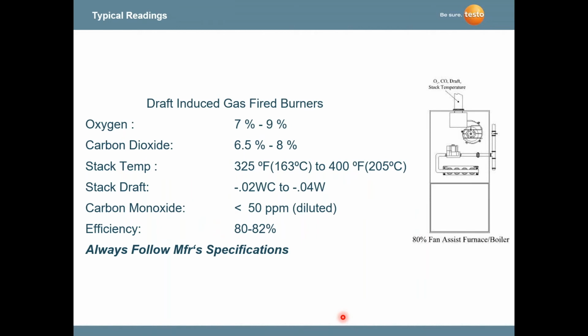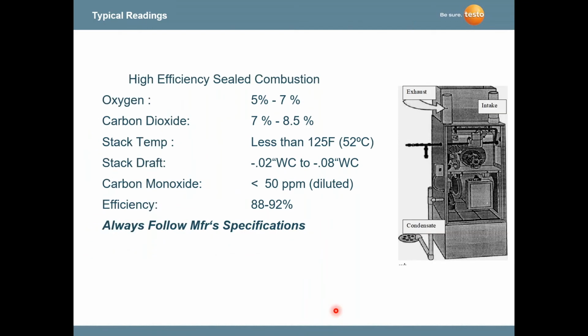Draft-induced gas-fired burners, again, here are some areas. Now, you may have your own specifications on this equipment already, but again, it should be somewhat close to what you see here. Again, this is done by a survey of gas and oil burner manufacturers and what they recommend on their burners as far as combustion efficiency and the measurements of flue gas.